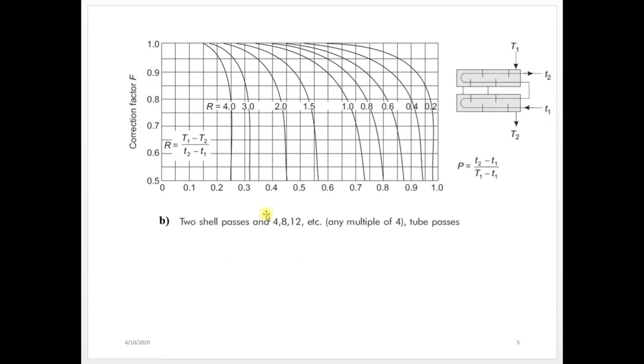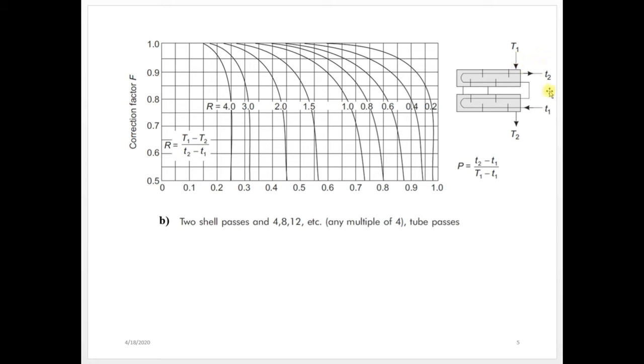The second graph is for 2 shell passes and 4, 8, 12 — that is any multiple of 4 tube passes. Correction factor F can be found out with the help of P value and R value. One more thing to remember: capital T refers to shell side temperature, and small t refers to tube side temperature.